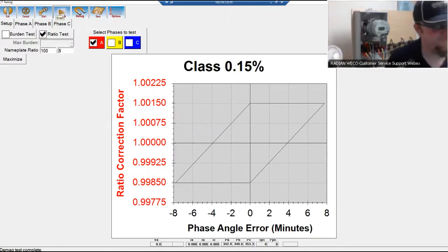Demag sends signals out to your CTs to run a demagnetization. The RW quickly ramps up and ramps down burden to attempt to demagnetize your CT.